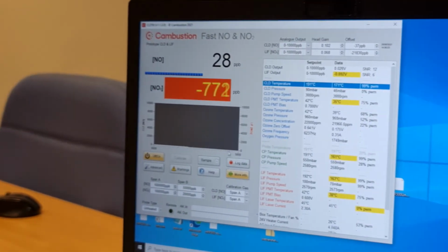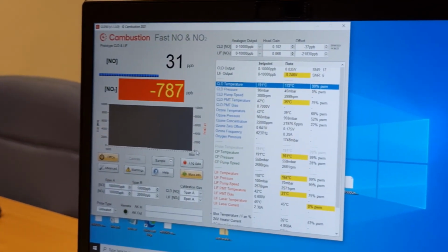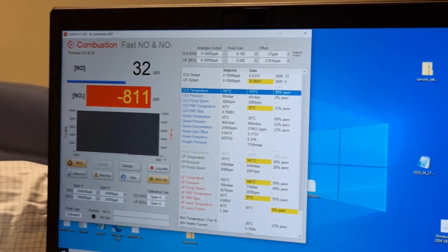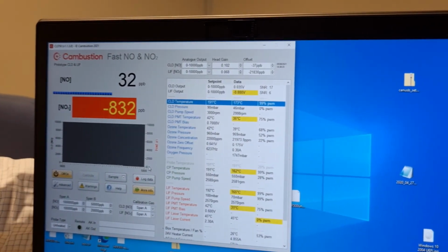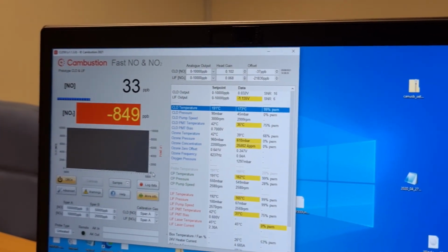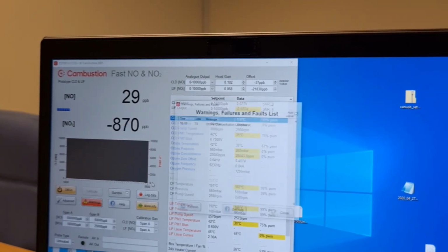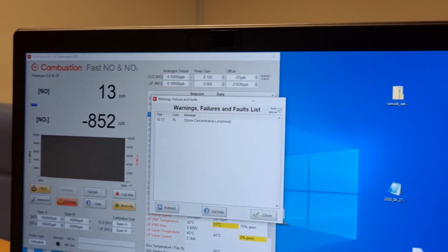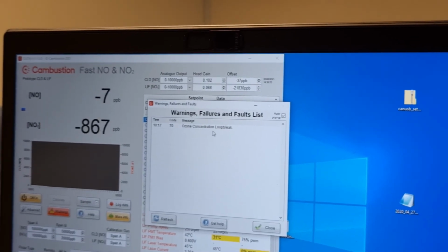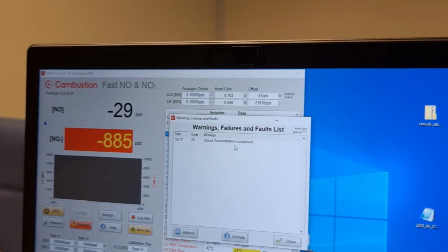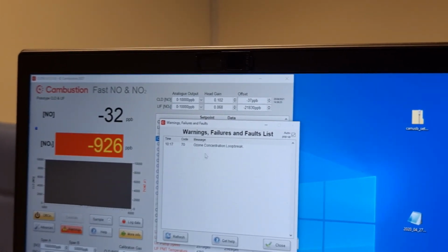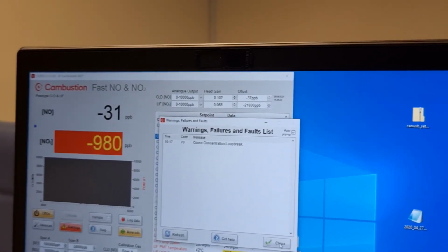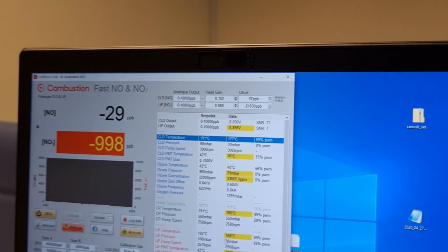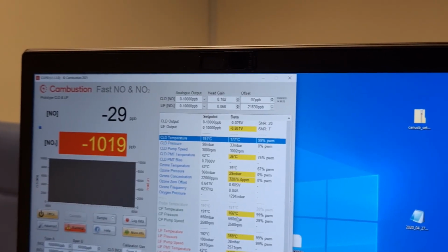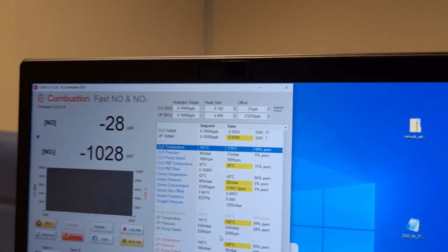So if I propagate a fault by disconnecting the oxygen inlet, for example, the analyzer, once it's depressurized, will show that there has been a fault. So the ozone concentration is not correct because there's no oxygen connected. This auto pops up so that you can see that there is a fault, and then by opening the head info window we can help diagnose what the cause of the fault is.